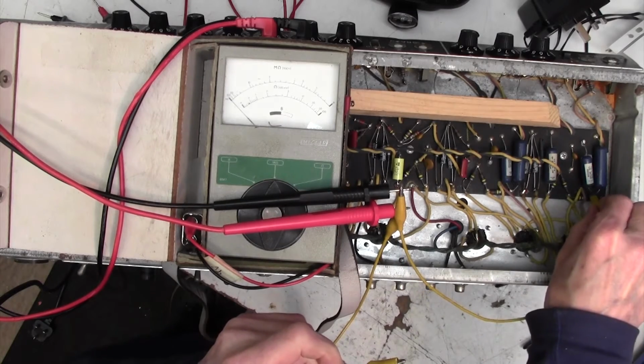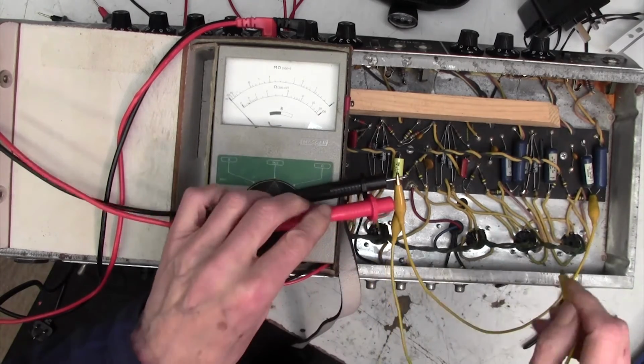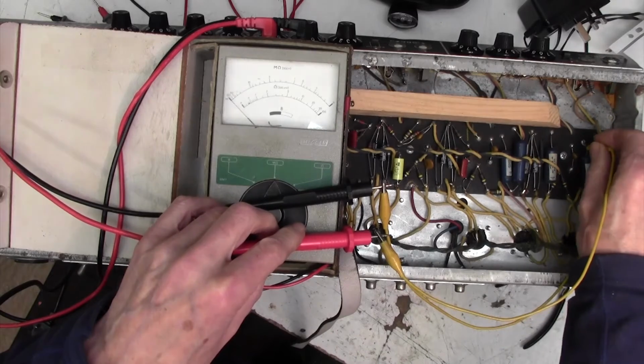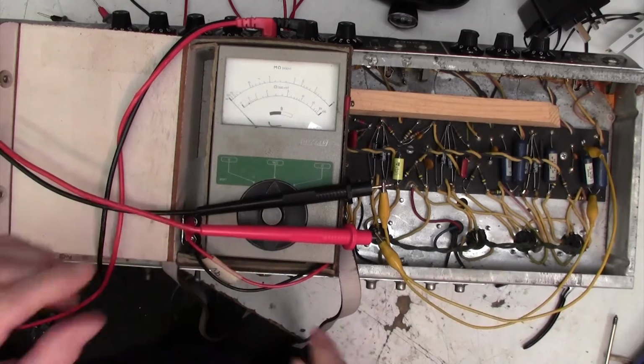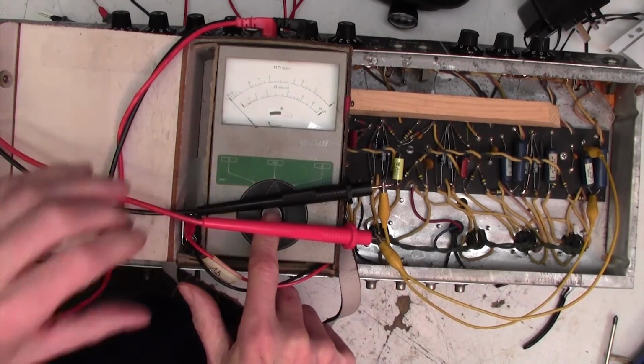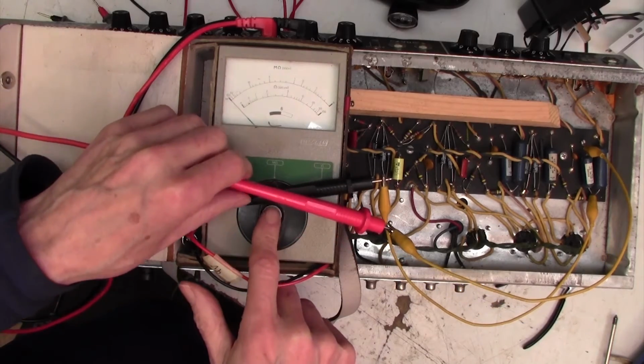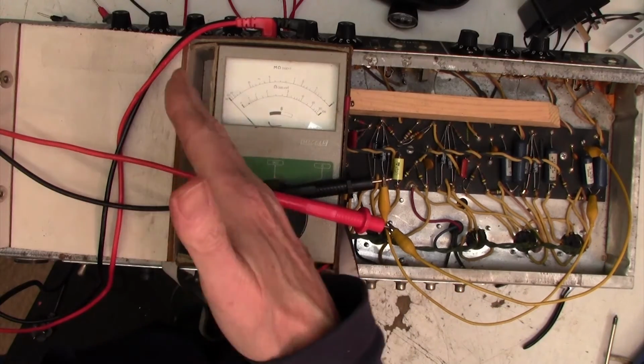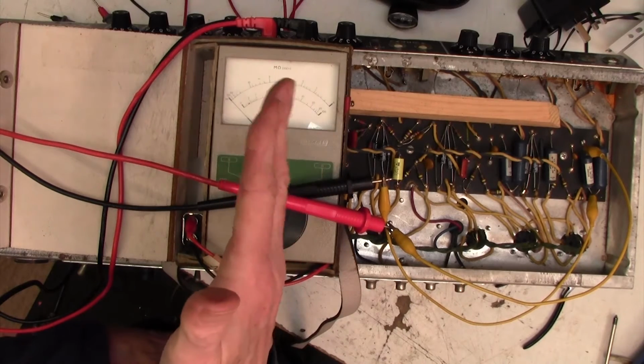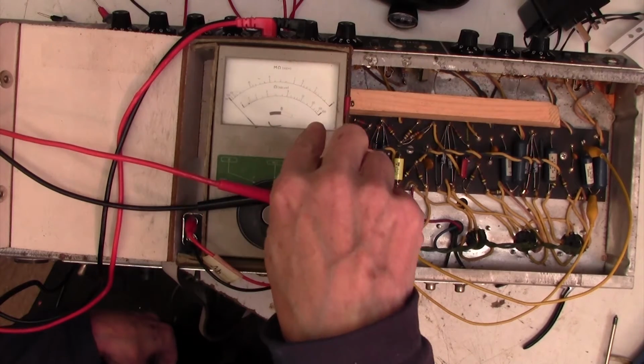You just clip one end to one side of the capacitor and the other end to the other side of the capacitor. Now when I press this button, it will put 500 volts across that capacitor, and the meter will tell me any current that's being drawn. In other words, it gives me a measure of the resistance.